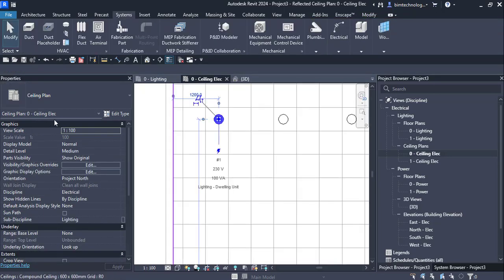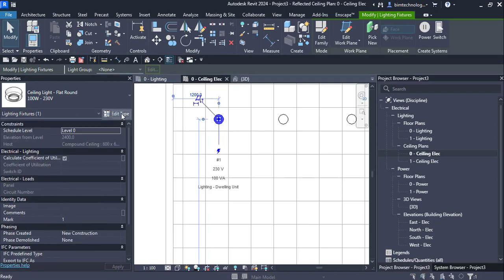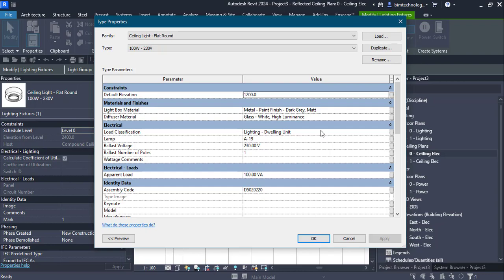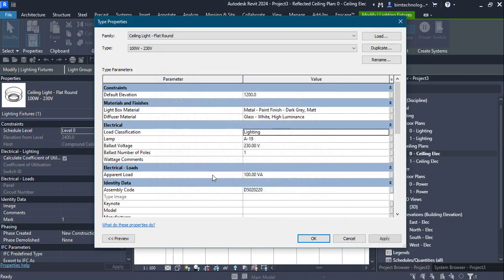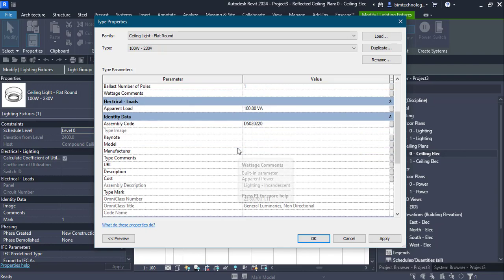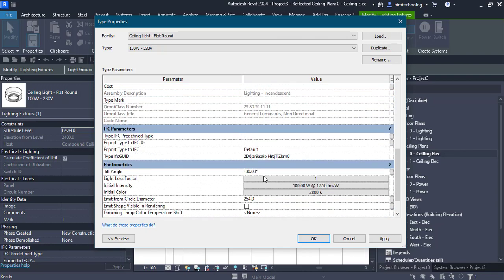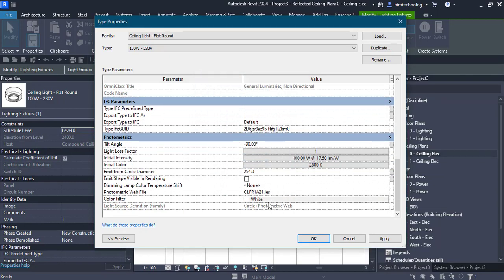Looking at the lighting fixture properties, go to Edit Type and you can see the load classification — it says Lighting - Dwelling Unit. You can change the load classification to Lighting, and the demand factor can be changed as required. Similarly, the apparent load, assembly code, and lamp can be edited. You can select lamp A19 with a ballast voltage of 230 volts. You can also do photometric editing: change the initial color, light loss factor, initial intensity, and other photometric values.